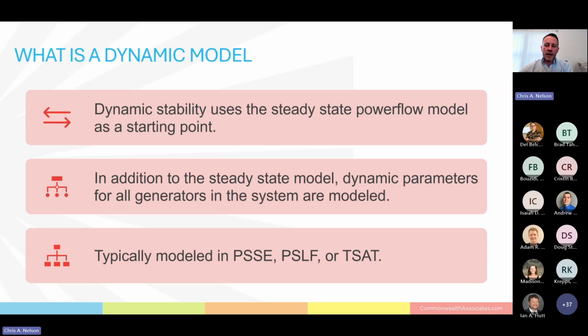For a conventional generator, it'll usually have generator parameters you can use to create the dynamic model file. If it's an inverter-based generator, that information usually has to come from the inverter manufacturer. They'll give you a dynamic file with all the dynamics in it, and you pair that with a power flow model of the site.